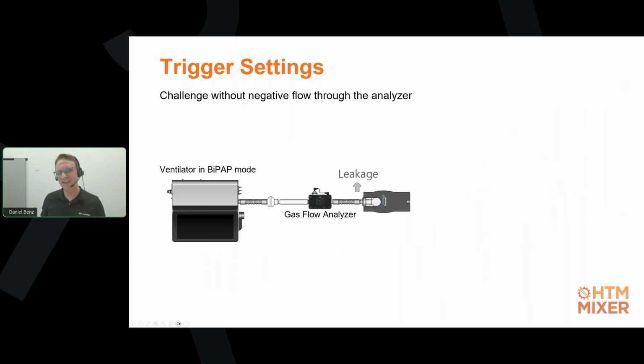But now we need to talk a little bit more in detail, because I also want to let you know that sometimes you will find applications where it matters. And then you need to understand how you can set the trigger settings. So in this example here, we have a BiPAP ventilation. And in such test setups, typically the ventilator delivers gas to the test lung with pressure. And then that gas actually leaves the test lung through a leakage in front of the gas flow analyzer on the side of the test lung.